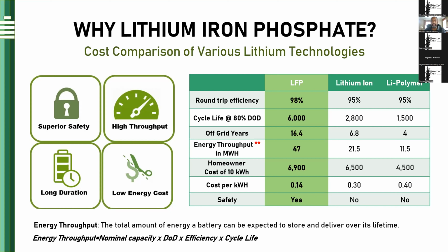When you look at lithium batteries and talk about safety, the failure point in an NMC battery, temperature-wise, you can put a lithium ion battery cell in an oven and it would catch on fire. But you could take an LFP battery cell, put it in the oven and turn it all the way up to 500 degrees, and the LFP battery would not catch on fire. So there is literally about a 500 degree Celsius temperature variance.